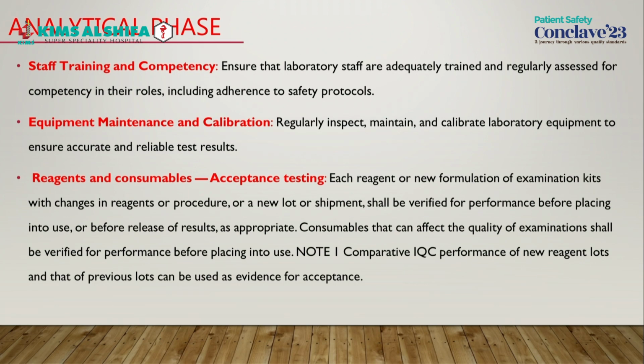What calibrator he has used, what number of calibrators he has used, and how he has compared his calibration data with the performance qualification. That is the crux of calibration. How much time he spent, what parts he took out and cleaned, raw data. Any calibration of the equipment in your lab should be supported by raw calibration data. Unless the company person provides you raw calibration data, you don't accept the calibration certificate. The calibration certificate is the document which ensures that all your measuring parts of the machine are measuring the analyte properly.